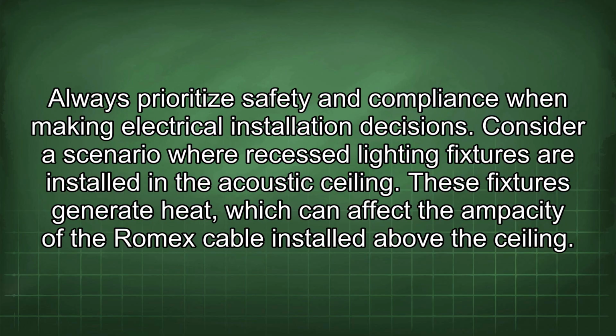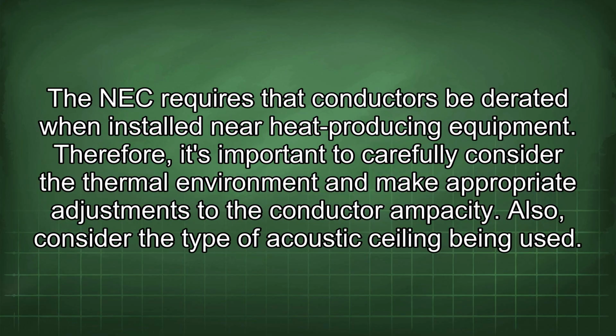Consider a scenario where recessed lighting fixtures are installed in the acoustic ceiling. These fixtures generate heat, which can affect the ampacity of the Romex cable installed above the ceiling. The NEC requires that conductors be derated when installed near heat-producing equipment. Therefore, it's important to carefully consider the thermal environment and make appropriate adjustments to the conductor ampacity.